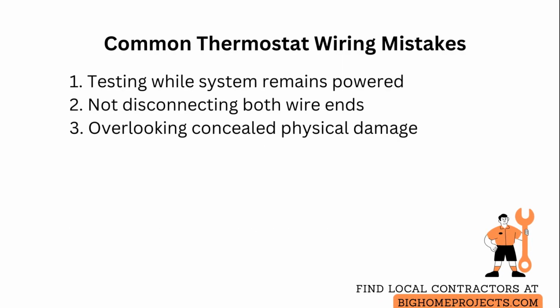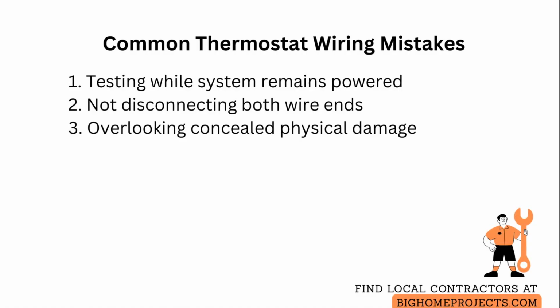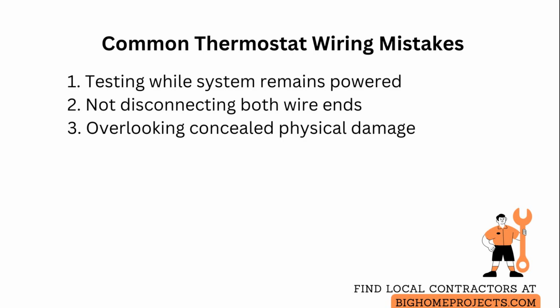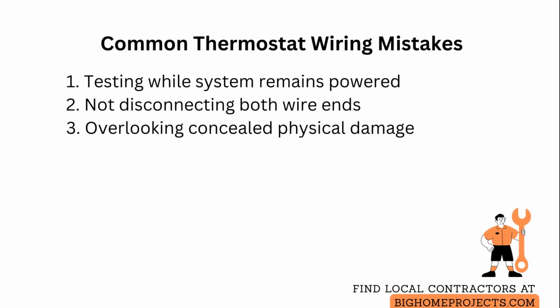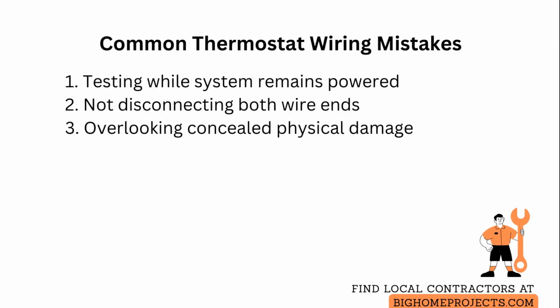Common mistakes include testing with the system powered, which can give false readings and risk damage, so always power down first and verify there is no voltage present. People often forget to disconnect at both ends and get misleading continuity through equipment circuits, so isolate wires at both the thermostat and furnace before measuring.